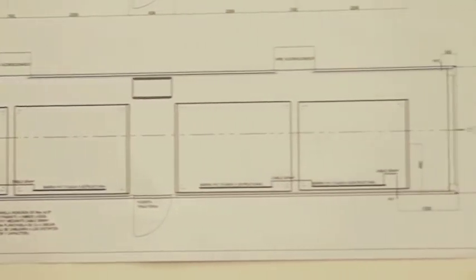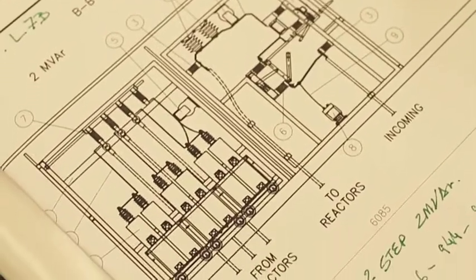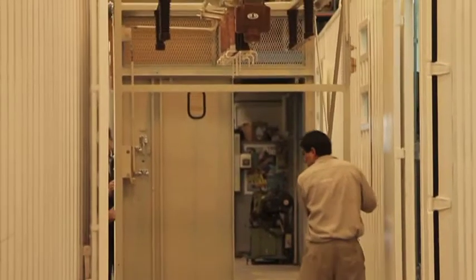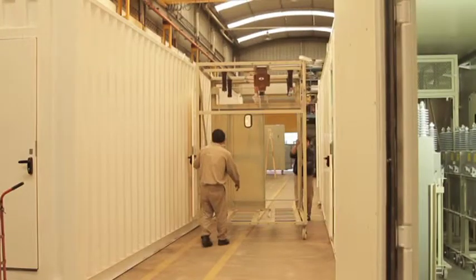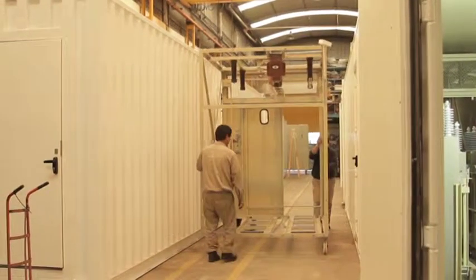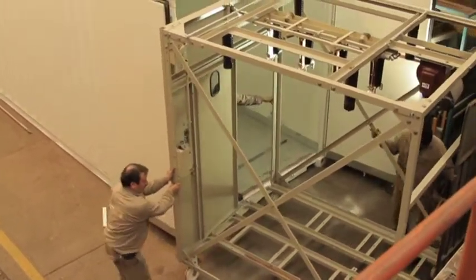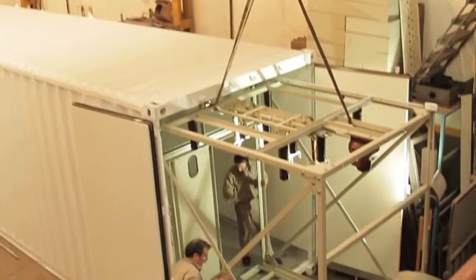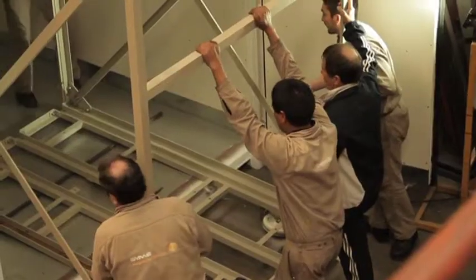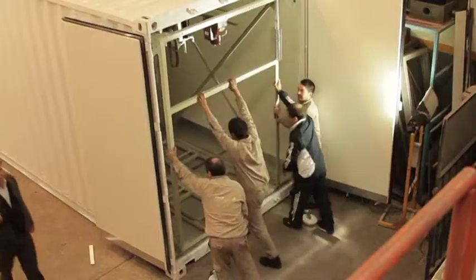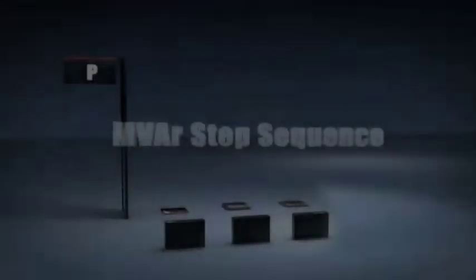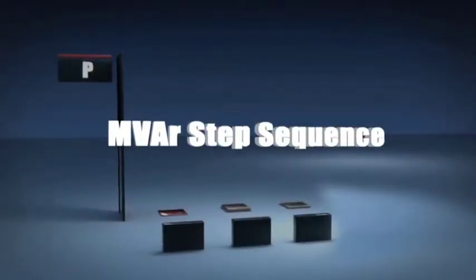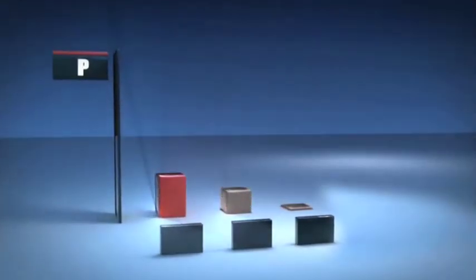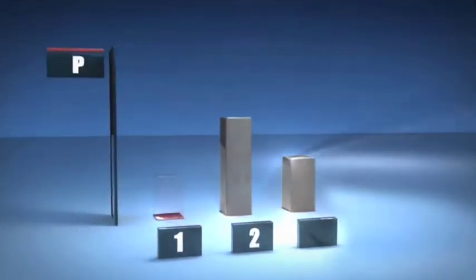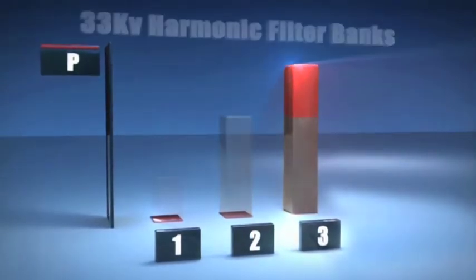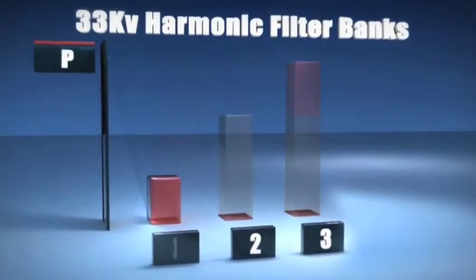The use of containers as mobile electrical rooms also served the purpose of safely transporting factory-assembled harmonic filter banks over almost 15,000 kilometers, including several intermediate transshipments, so that the erection at the job site could be completed in a very short period of time and with a minimum of civil and electromechanical works involved. Harmonic filters were conceived with 3 stages in a 1-2-3 output ratio. For example, for the 33 kV filters, a 3-6-9 megavar sequence was chosen.